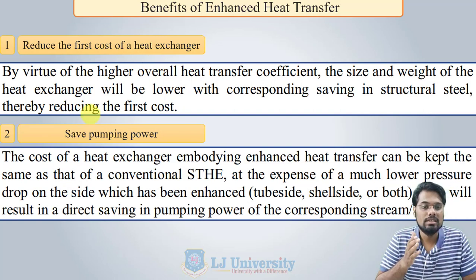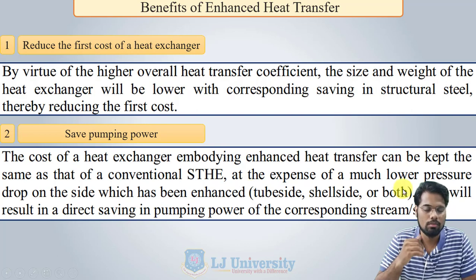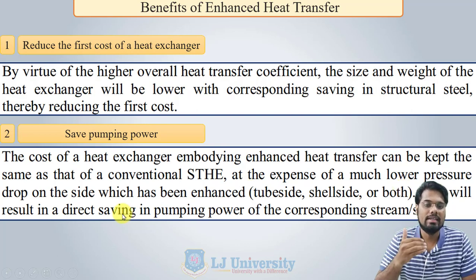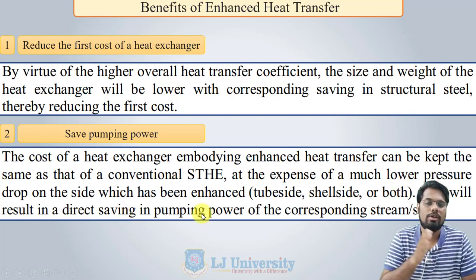The cost of the heat exchanger embodying enhanced heat transfer can be kept the same as that of a conventional shell and tube heat exchanger at the expense of much lower pressure drop on the side which has been enhanced, tube side, shell side, or both. This will result in direct saving in pumping power of the corresponding streams.